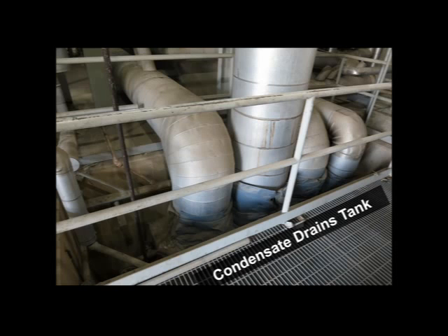So the problem here was the condensate drains tank. There's all of these drains that go into this tank down here. It's a high temperature tank. It takes a lot of abuse from thermal energy. And then this tank vents into the condenser. And so all of these drains come in. It's kind of abrupt. There can be an abrupt dump of load or water or steam into this tank, and then it gets vented. It's constantly vented out to the condenser.